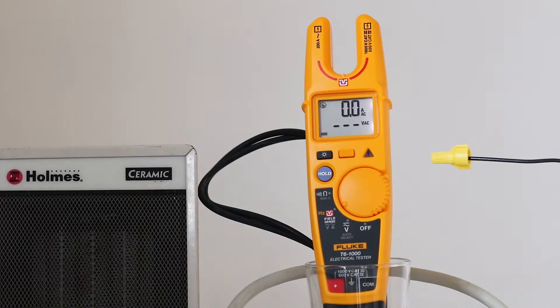The Fluke T6-1000, according to manufacturer's specifications, is rated to measure 1000 volts AC or DC and 200 amps in the current mode. It is okay for 1000 volts in a CAT 3 location and 600 volts in CAT 4, where there is greater available current.